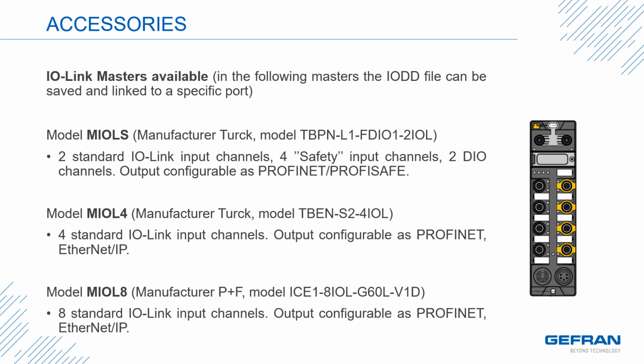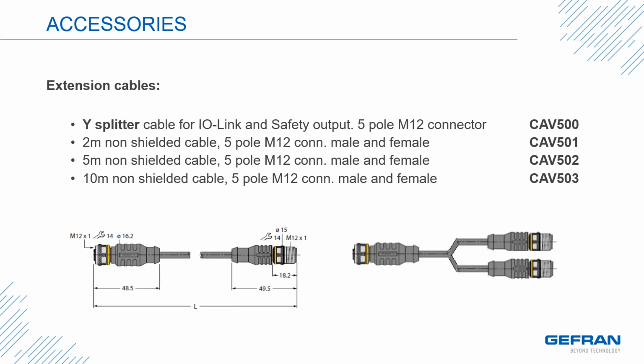The I/O link master stores the I/O device description file for each of the connected devices and also allows it to be linked to the specific port that the device will be connected to. Gefran doesn't manufacture I/O link masters, but we offer several versions from different manufacturers in our catalog for ease of accessibility. We also offer a selection of extension cables for the I/O link specification in various lengths, including a Y splitter, which is used when your particular I/O link sensor is configured with a safety relay or safety analog output to separate that from the standard I/O link output.